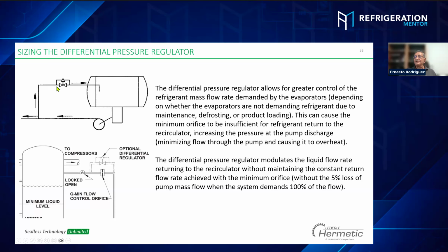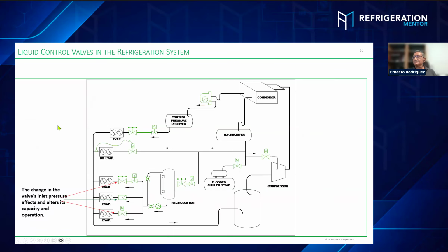And the regulator is sized according to how many gallons per minute you want to move. It can be a 3/4 inch, 1 inch, or 1 1/4 inch port. Okay, this is the advantage, the beauty of this device. It means one more thing, you keep your constant pressure. You want to have a pressure on your hand expansion valve on your system. I want to explain in the next slide.